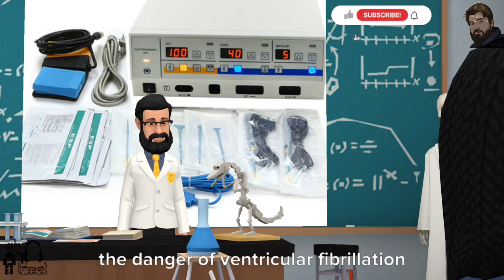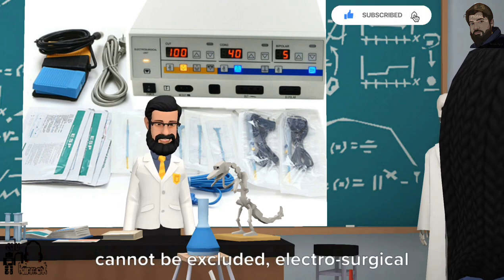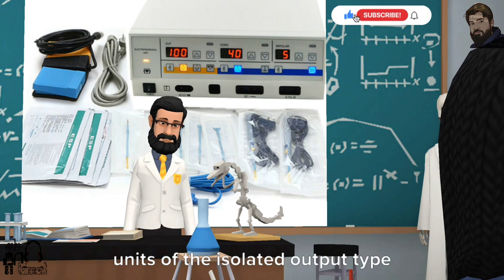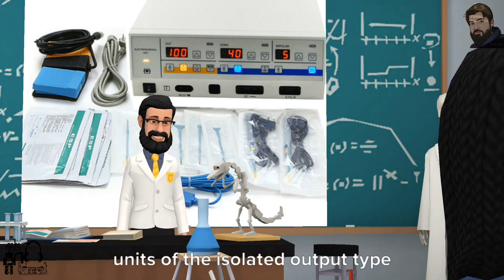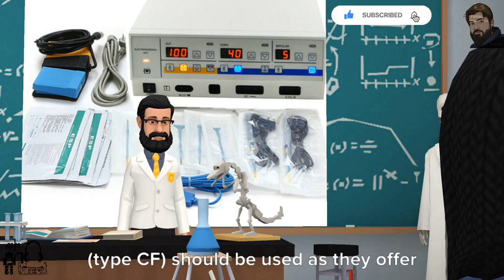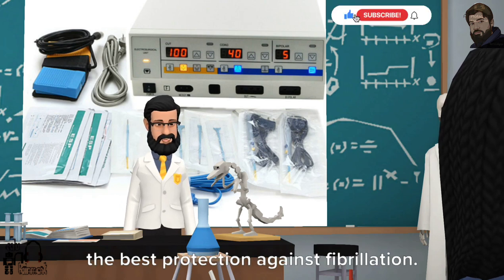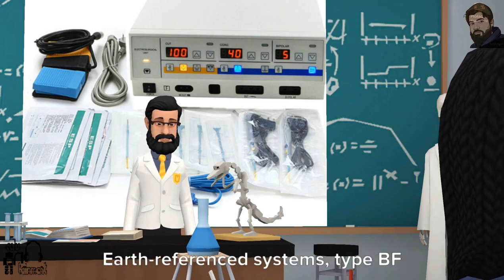For surgical applications in which the danger of ventricular fibrillation cannot be excluded, electrosurgical units of the isolated output type (type CF) should be used as they offer the best protection against fibrillation.